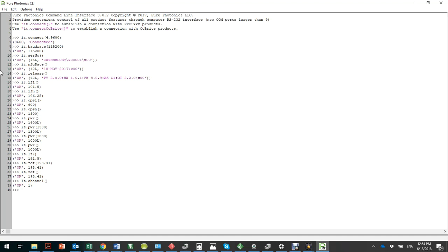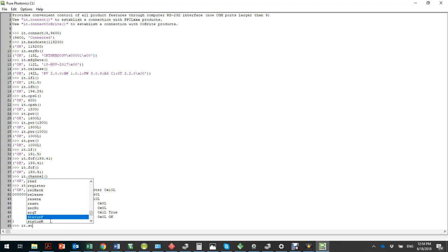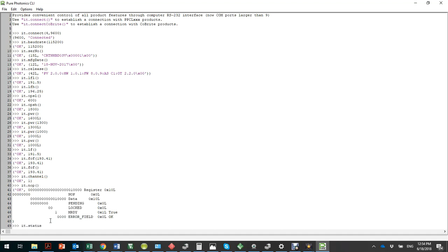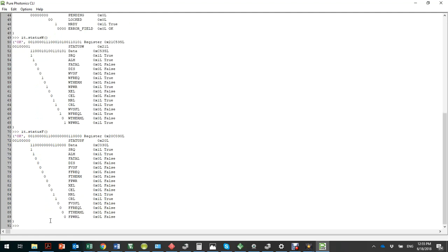If we want to read the laser state, we do it.NOP — that says no operation, and we see no pending bits, which means the laser is waiting for a command. We can also read status registers: it.StatusW is warning and it.StatusF is fatal. You can see here there are a couple of latching bits, which means that at some point in the past that warning or fatal bit was raised, but now it may not be anymore, and we may want to set those back to zero.